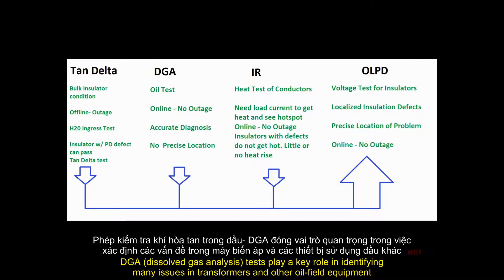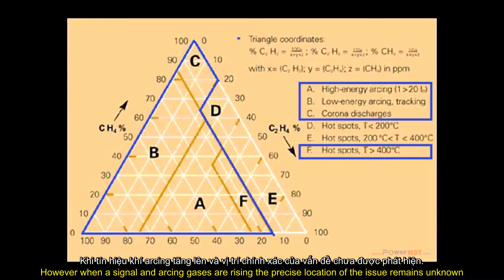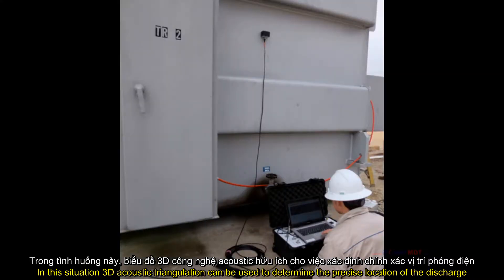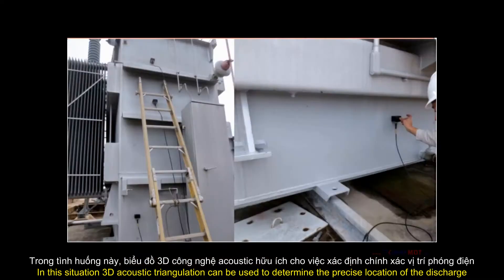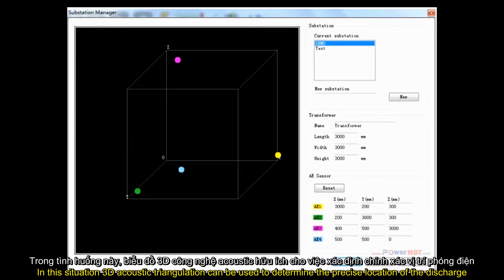DGA tests play a key role in identifying many issues in transformers and other oil-filled equipment. However, when acetylene and arcing gases are rising, the precise location of the issue remains unknown. In this situation, 3D acoustic triangulation can be used to determine the precise location of the discharge.